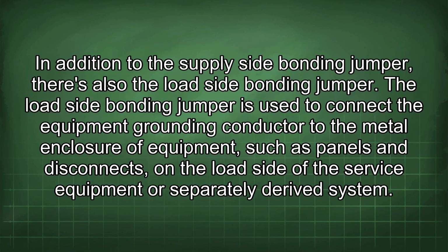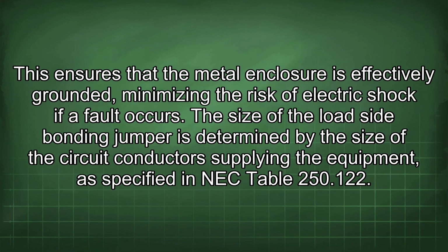In addition to the supply-side bonding jumper, there's also the load-side bonding jumper. The load-side bonding jumper is used to connect the equipment grounding conductor to the metal enclosure of equipment, such as panels and disconnects on the load side of the service equipment or separately derived system. This ensures that the metal enclosure is effectively grounded, minimizing the risk of electric shock if a fault occurs. The size of the load-side bonding jumper is determined by the size of the circuit conductors supplying the equipment, as specified in NEC Table 250.122.